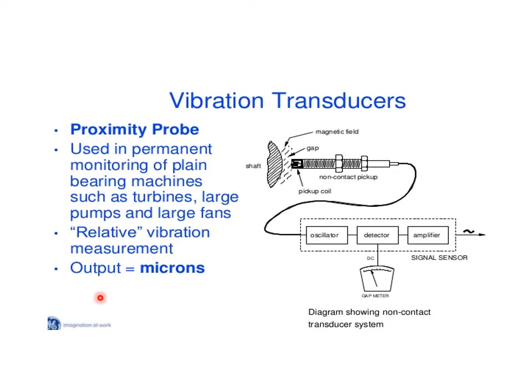Here is a schematic diagram of a vibration transducer. Here a shaft vibration is monitored. It also makes use of the magnetic field, and here also you can see the cable you are taking, and there is an oscillator, detector and amplifier. Here you can get the reading as a meter reading. So it is used in permanent monitoring of plain bearing machines such as turbines, large pumps, large fans. Example, BHEL and all, where they are using turbines, big fans and big pumps. They are widely using this vibration probing equipment. We can have a relative vibration measurement also. Output can be even in a minute scale, up to microns.